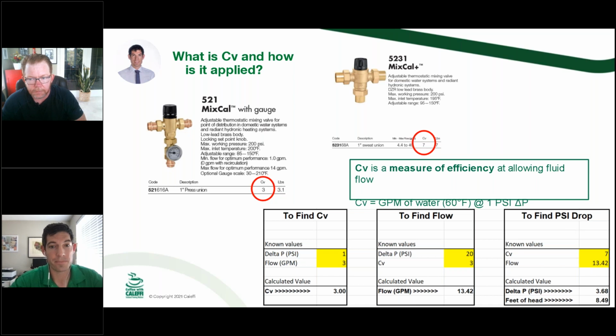So CV of 3. Now go to the middle one, where we can plug in those other numbers. All 3 of these are related. So if we say we can measure a 20 PSI drop across that valve, it's a CV of 3 valve, we know that from the literature. So the calculated flow of 13 GPM has a pretty big penalty there in PSI. Usually no more than 5 or 10 is what engineers will look for in a mixing valve. So we can do it, but we're taking a pretty big pressure penalty to get up to that 13.42 GPM.